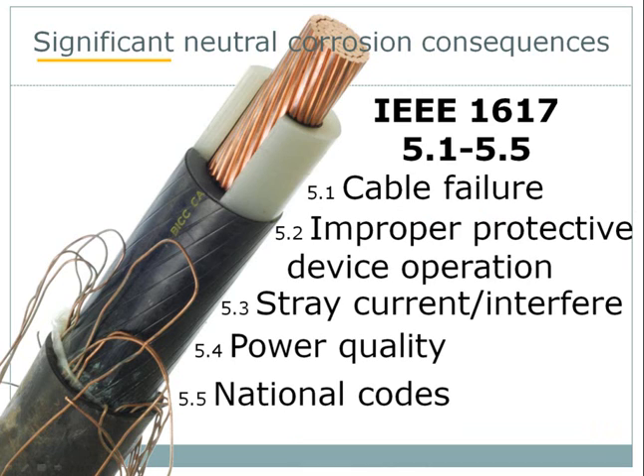The other four consequences include: if you lose the neutral, it results in higher circuit impedance — protective coordination can suffer, which can in turn result in more extensive damage from a fault. Number three, the loss of significant neutral may result in charging current, fault current, and system neutral current flowing on the conducting path of adjacent metallic facilities. The higher impedance can also present a higher step or touch potential in connection with a dig-in, and even with stresses and voltages like those experienced by our cow a few moments ago.